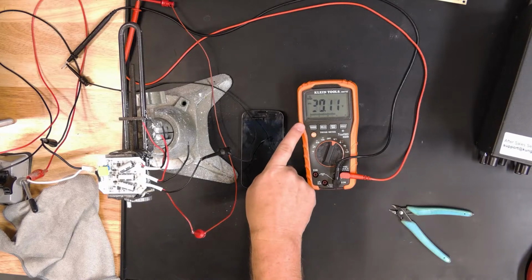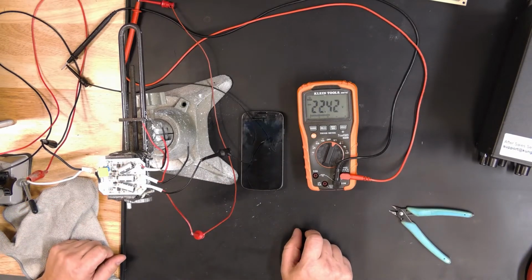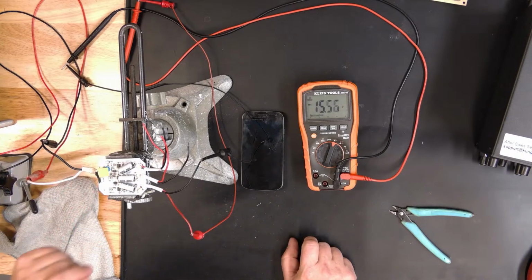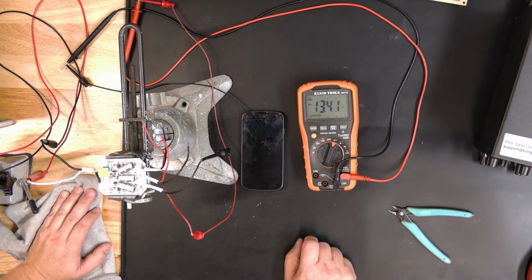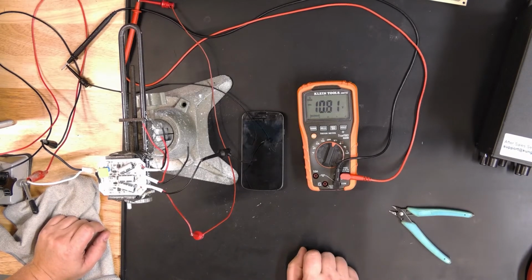Okay, you can see it bleeding off right here. That is actually these large capacitors discharging up here in the DC side. That's why you never want to grab a hold of a circuit board that's been powered off until you know that it's bled down. Goes to show you right there.